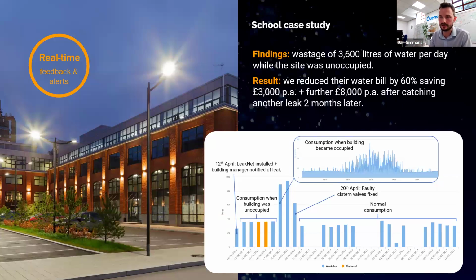So they kept it in, and only a few months later more urinals failed - that was even more, £8,000 a year. It was an important lesson for them: fixing it today doesn't mean it's fixed for life. Having a continuous system that automatically alerts is important, because this could have gone on for years, wasting over £10,000 a year without an automatic system.